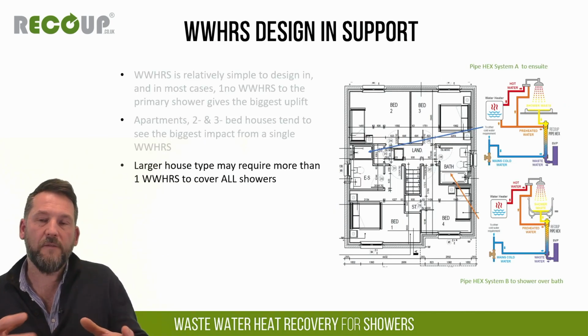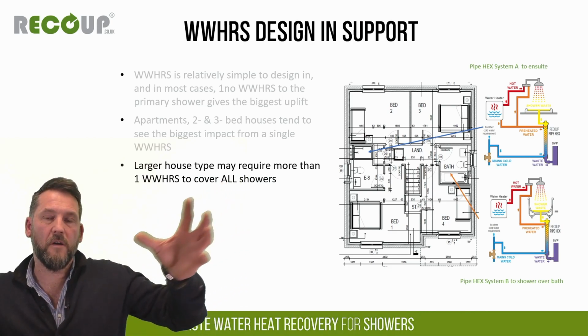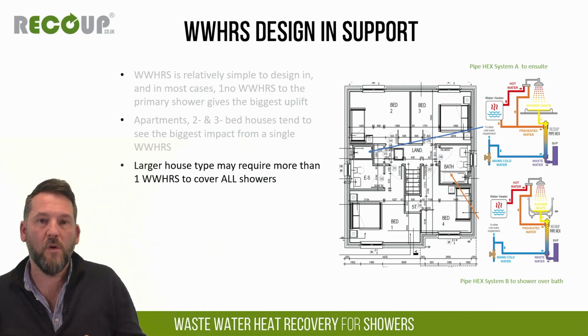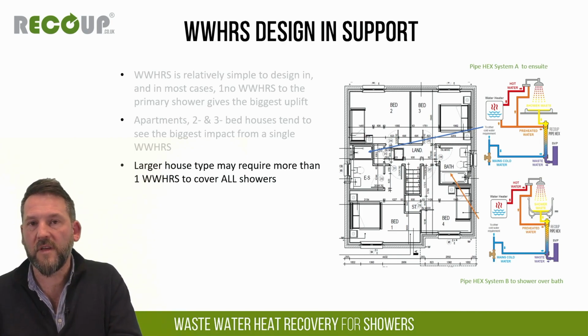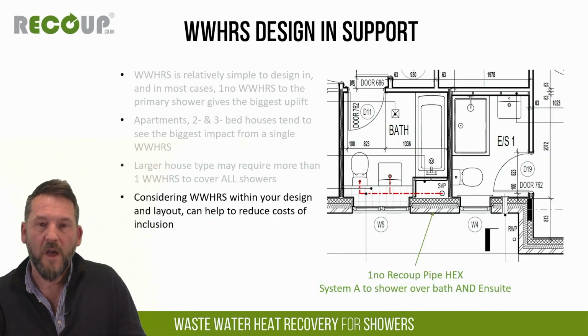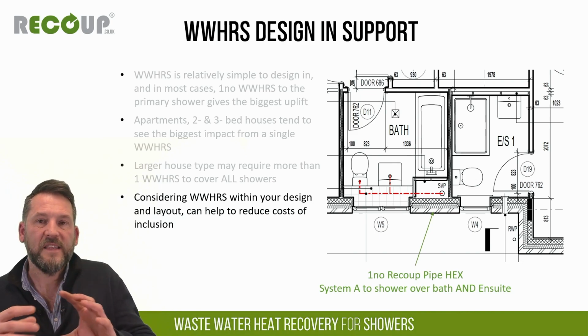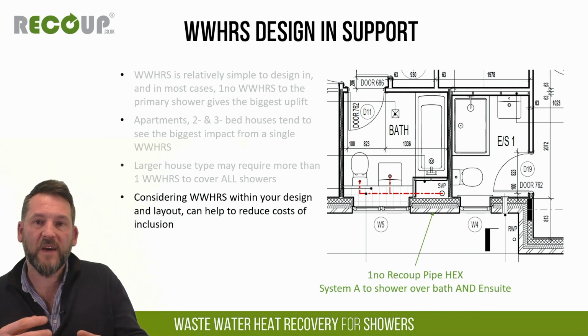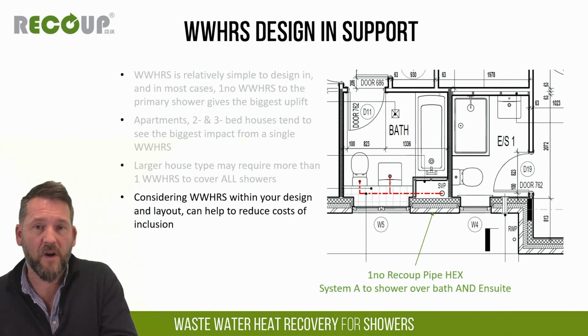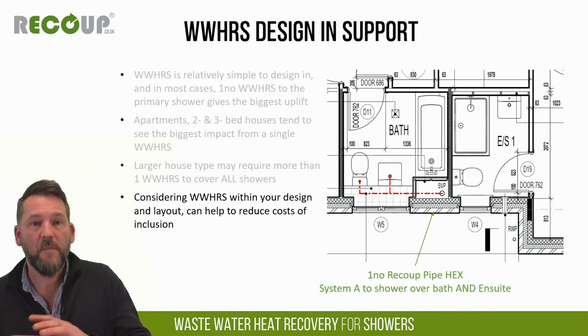If you have a very big house with showers on different sides, you might need two or more wastewater heat recovery units. Normally it's one installed as System A, anything else as System B, giving maximum coverage and impact. But if you design your bathrooms back to back, you can probably get two showers, a shower-over-bath and an ensuite shower, into one pipe, reducing cost while maximising impact.